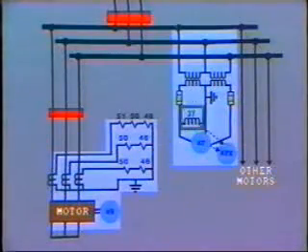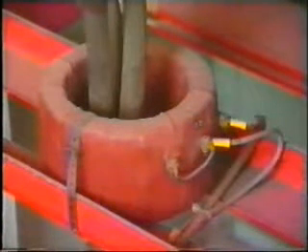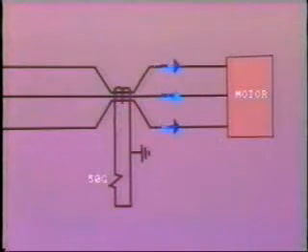As we mentioned earlier, insulation failure usually leads to a stator ground fault. The best way to detect this is through the use of a toroidal CT, which is connected to an instantaneous relay. All three supply leads to the motor pass through the window of the transformer. As long as the three currents are balanced, the value of CT secondary current is close to zero.